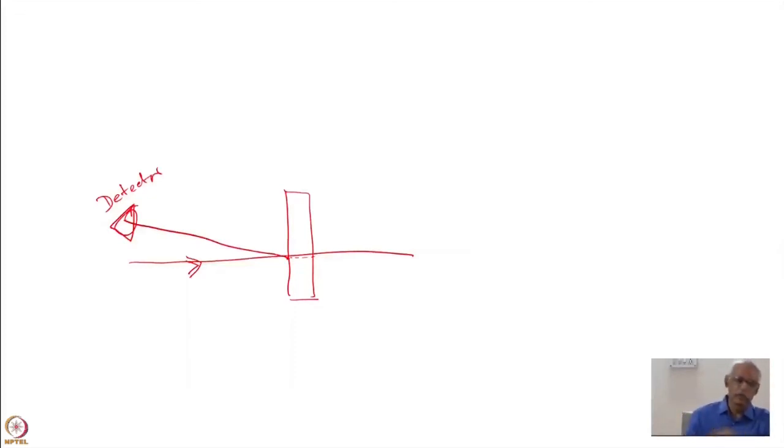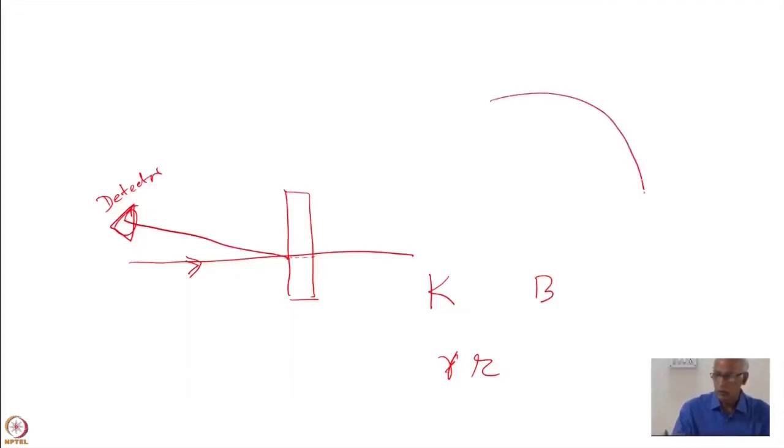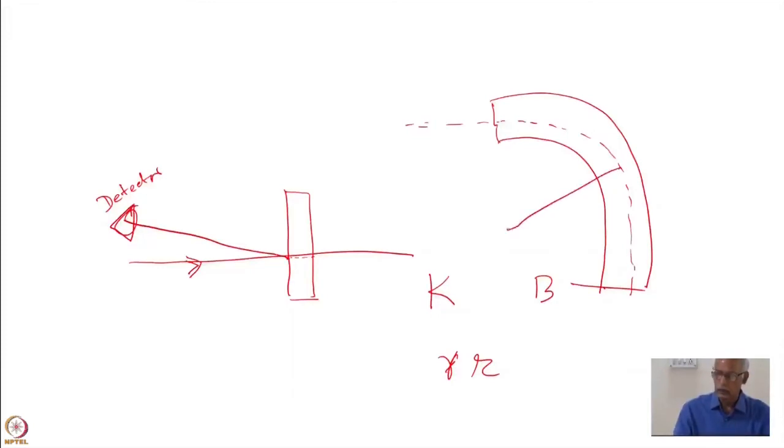So the K value which we are determining, whether by using the aluminium (p,gamma) reaction, or any neutron threshold experiment, or this backscattering experiment, we are measuring the K value. And for the K value, we should know this precisely, and other parameters like the R value. Because if the beam is coming, suppose through a magnet like this, and it is following the central trajectory, then the radius of curvature is well defined. But if it is coming like this, with the beam heavily diverging, then it need not be the same. So we have to well define it.